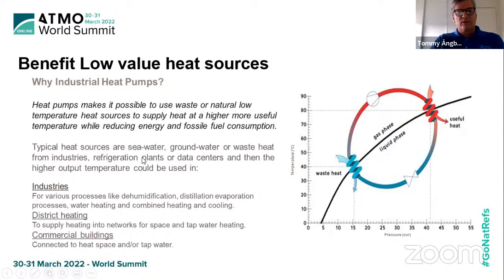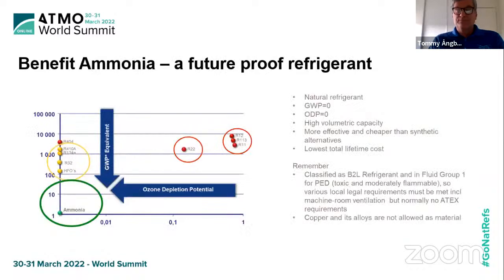This we did with the refrigerant that we like very much, that's ammonia. For this size of machines, ammonia is really a future-proof refrigerant. It's well known. It's a natural refrigerant that we are talking about in this ATMO conference, with a global warming potential of 0 and ozone depletion potential also at 0. Of course, most refrigerants are already doing that, but the global warming potential is important. And it's also a very efficient refrigerant with high volumetric capacity, and it's more effective and also cheaper than synthetic alternatives. So you can obtain a low total lifetime cost using this efficient refrigerant.